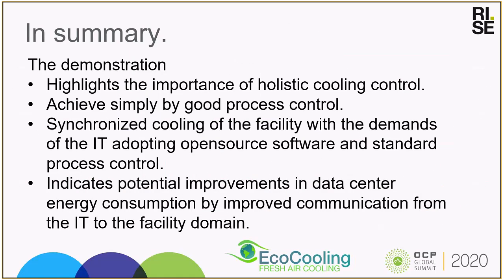So in summary, this demonstration has highlighted the importance of holistic cooling control. By simple process control, we can achieve this simply, but we need to synchronize the cooling of the coolers to the demands of the IT. And we've done this by adopting a number of open source software tools and standards within a process control loop. So this indicates that there's potential improvements in data center energy consumption by this improved communication.